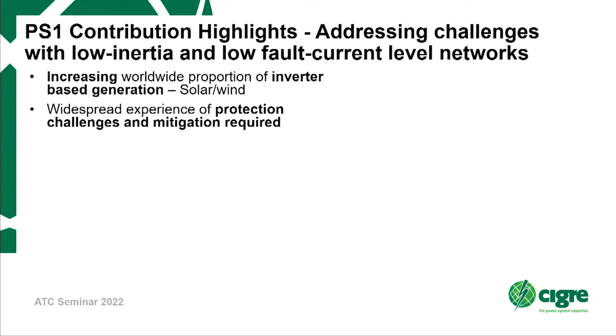Distance protection and under-frequency protection appears most affected. Utilities are often mitigating by adjusting settings or using different protection functions such as line differential. Based on experience of inverter-based fault characteristics and their effect, manufacturers are also making changes to protection algorithms.